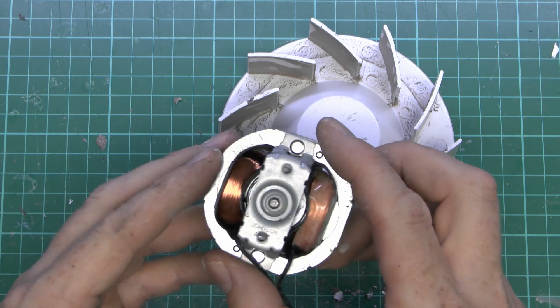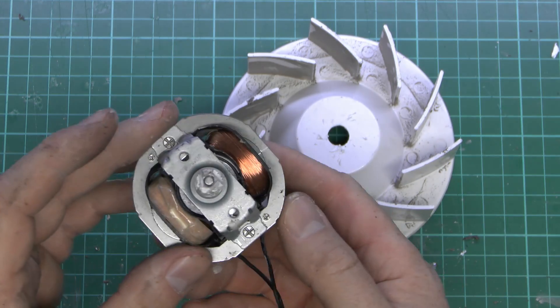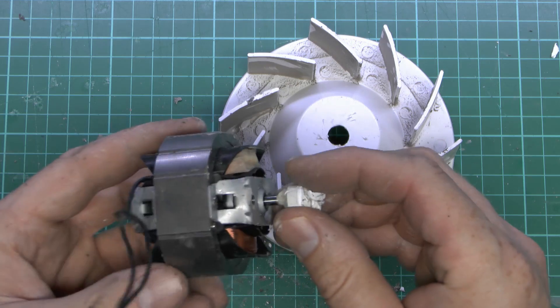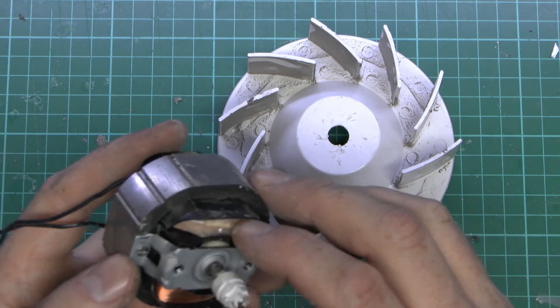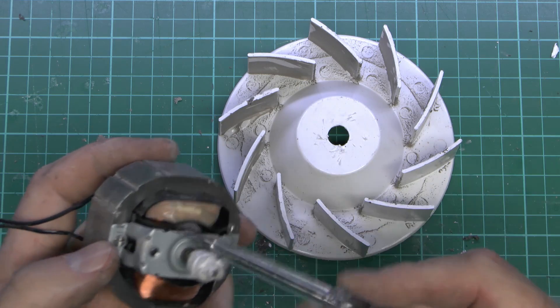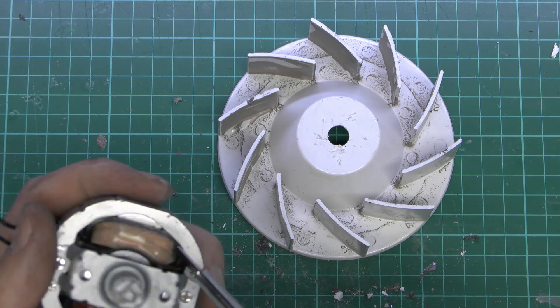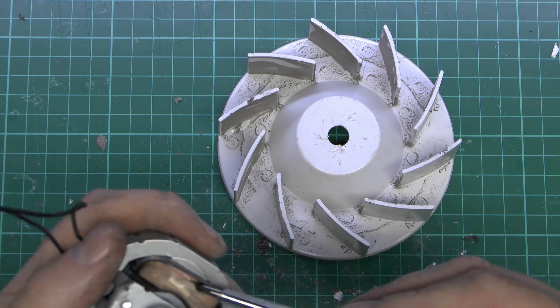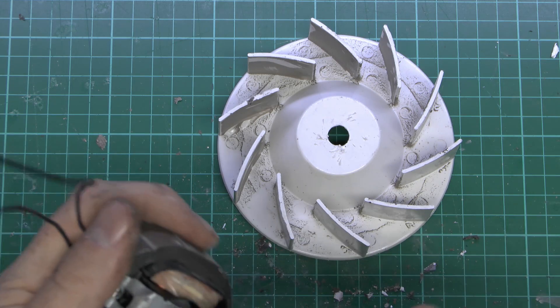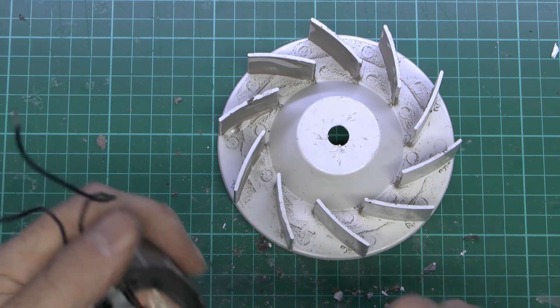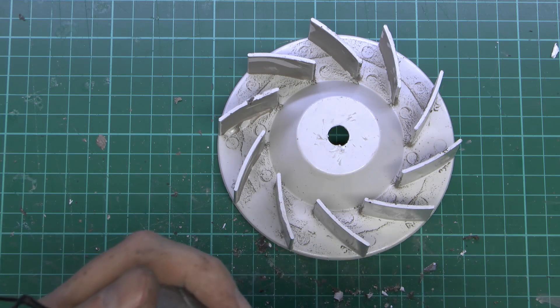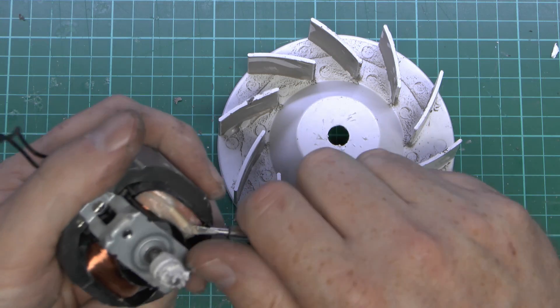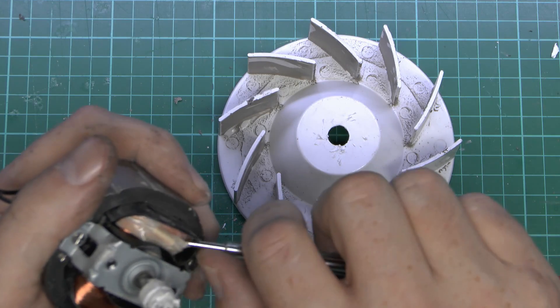There's Johnson on the back of there. And there's a few other numbers and things on it as well. As I say, this shows as open circuit, so obviously one of the windings has failed on this, or maybe the, probably a thermal fuse in there, which may well be the culprit that's actually failed. So I'm just going to get in there. Overheating of these things is not going to be uncommon, considering where they're actually installed in a lot of cases in a hot environment. And of course the motor itself does generate a certain amount of heat as well.